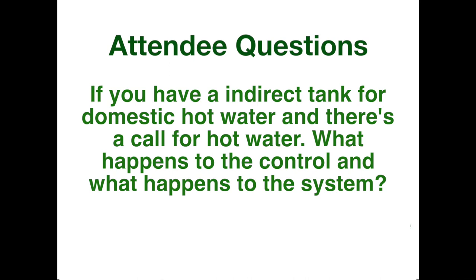So in this photograph, the tank on the right hand side is a Thermocon. Basically, it's the heating buffer tank, like a flywheel, right? The question is, you can't see the boiler in this photograph, but if you have an indirect tank for domestic hot water, and there's a call for hot water, what happens to the control and what happens to the system?